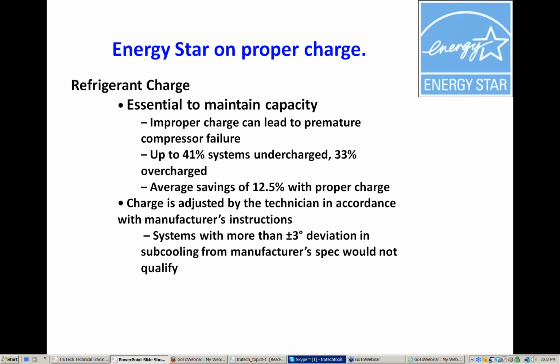What they found out is that refrigerant charge is basically essential to maintain capacity. And if we had improper charge, it was going to lead into premature compressor failure. In the studies, they found 41% of systems were undercharged and 33% overcharged, and that there was an average savings of about 12.5% with proper charge. And that charge had to be adjusted by the technician in accordance with manufacturer's instructions. And this is just something to keep in the back of your mind because we're going to talk about this later: systems with more than a 3-degree deviation in subcooling, we're talking about high-efficiency TXV systems now, would not qualify for the Energy Star rating. That was one of the big things that went through this.